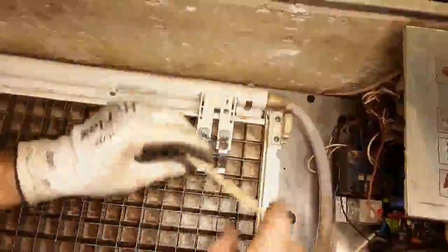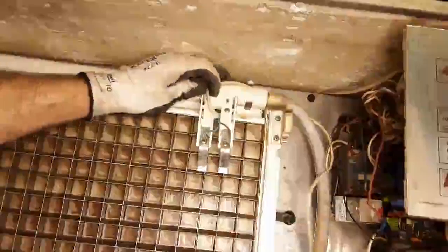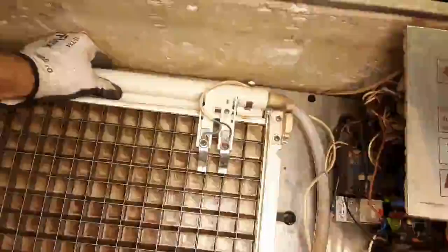The cascade goes back in reverse and just goes back on top here. This cable is very important — it can cause problems if it's too tight. It will pick up the sensor and you're going to get a false reading. What I usually do is, if there's a clip at the back I use that, if not I just clip it in with the cascade and give it a little bit of leeway, making sure that it falls naturally. If it's too tight it's going to give me a false reading, so I give it a little bit of leeway. That's perfect — my cascade is back.